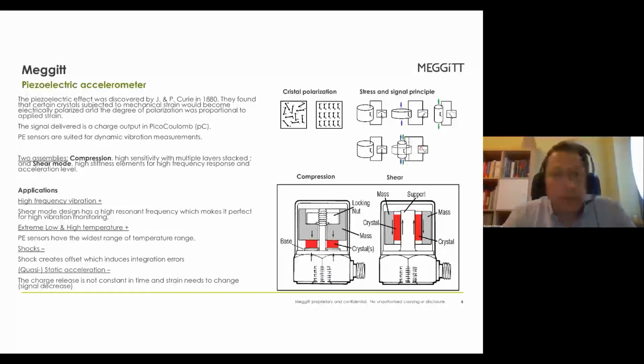Our design is compression or shear mode. These are pretty much in use for high frequency applications. That means that the units need movement. We cannot measure extreme low frequency, otherwise we have an uneven distribution of charge inside the crystal. As well, we cannot use them for shock applications, as residual stress induces an offset in the measurement, so measurement errors.